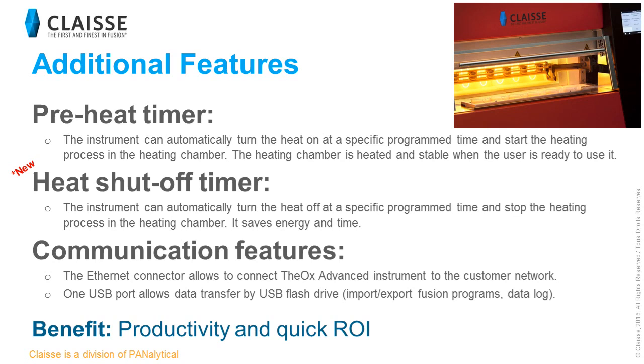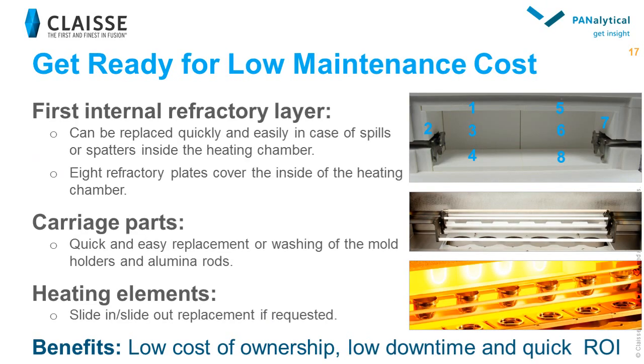The TheOx Advanced is network ready. An Ethernet connection allows the user to connect the instrument to the network, most likely their LIMS. As with the previous version, the first layer of refractory material inside the TheOx Advanced heating chamber is made of 8 different refractory plates, all of which can be removed and replaced. Consequently, there is no need to replace the entire heating chamber in case of spilling or spattering. Consumable parts such as the mold carriage and alumina rods can also be easily removed, washed, and replaced when required. Heating elements can easily be replaced by simply sliding them out of the heating chamber. This easy maintenance ensures a low cost of ownership and a quick return on investment.